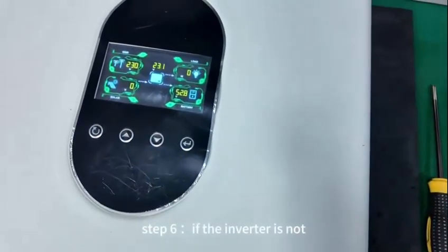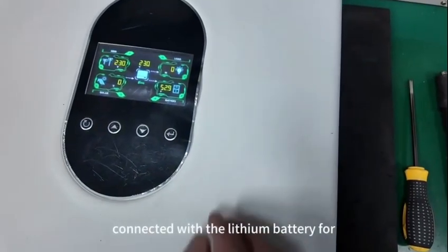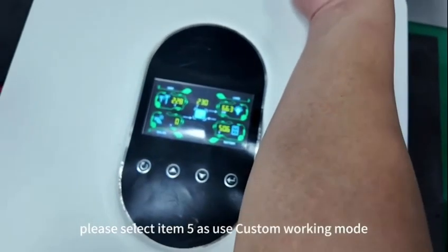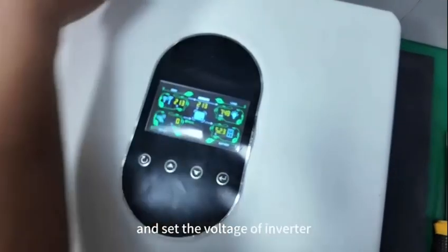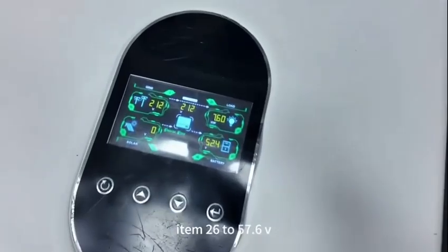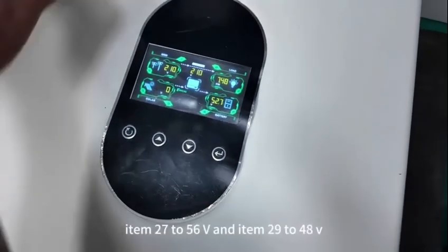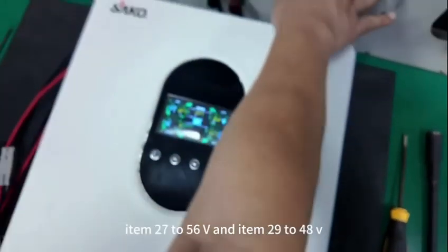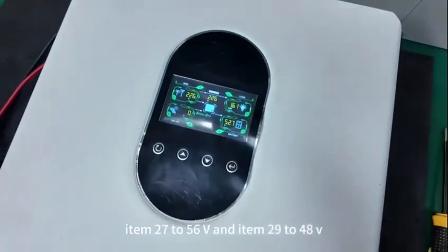Step 6. If the inverter is not connected with the lithium battery for BMS communication, please select item 5 as Use Custom Working Mode and set the voltage of inverter item 26 to 57.6 V, item 27 to 56 V, and item 29 to 48 V.